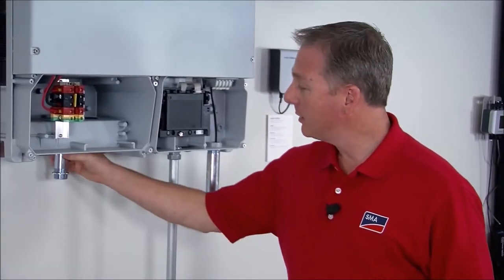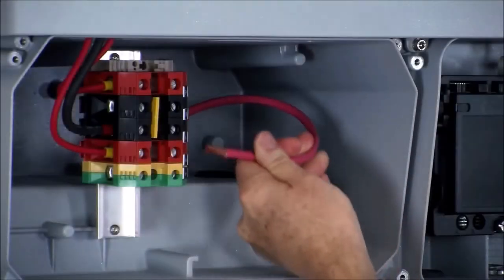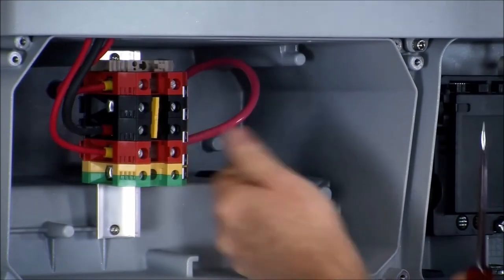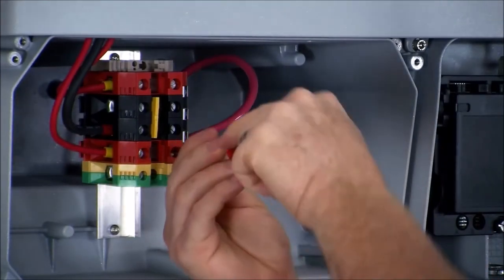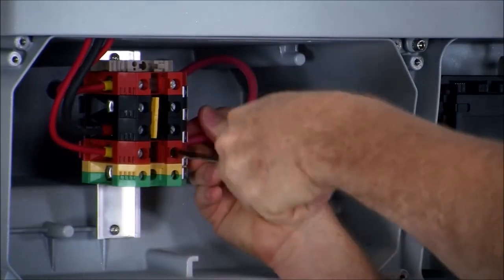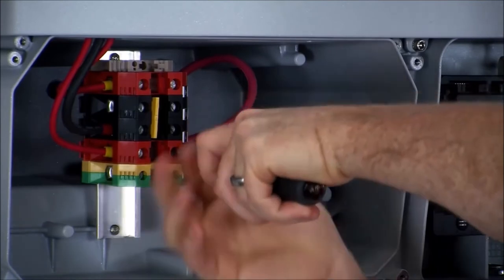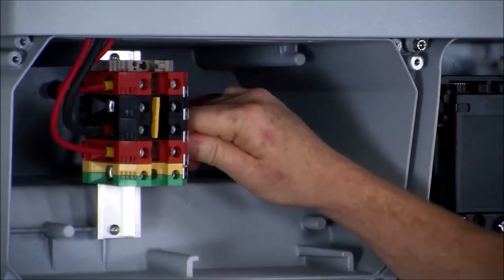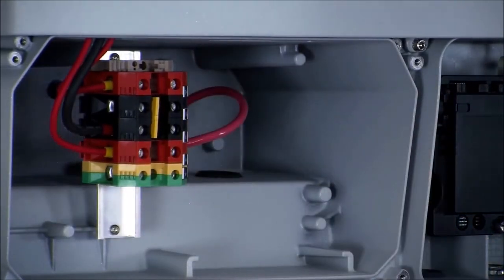Now I've got a piece of conduit here again just to show you how this would go and I'm going to connect these two conductors into the A positive and A negative terminals, meaning this string or set of strings will be going into the A channel maximum power point tracker inside the Tripower.